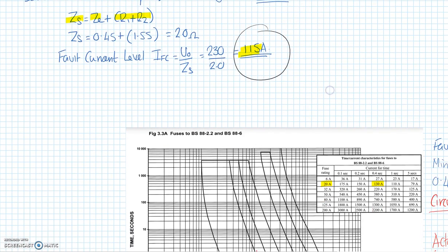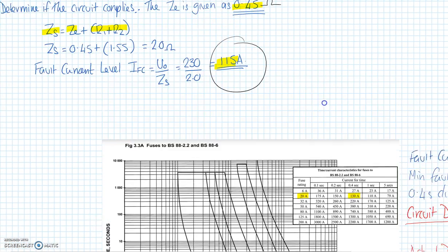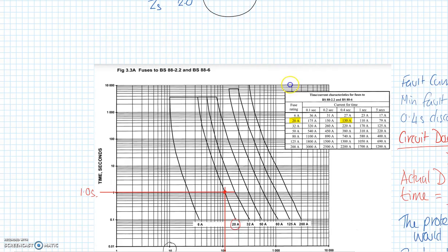Okay, so it's quite a high impedance. If I was testing that circuit, I would have alarm bells ringing at 2 ohms, because that is quite a high value.